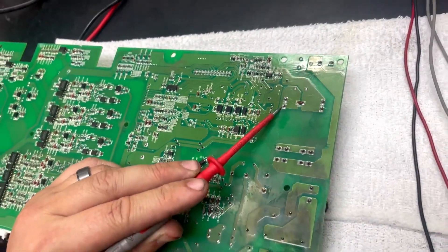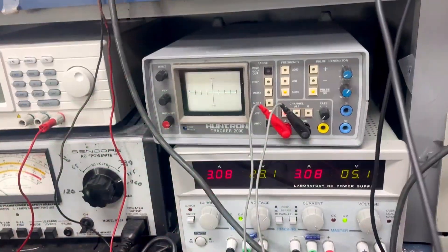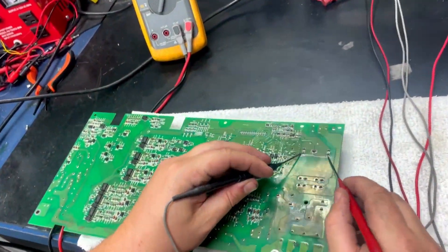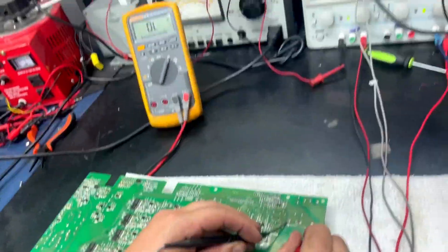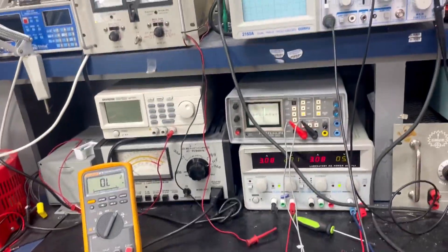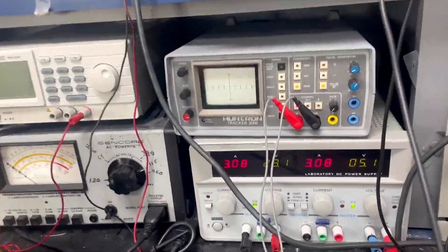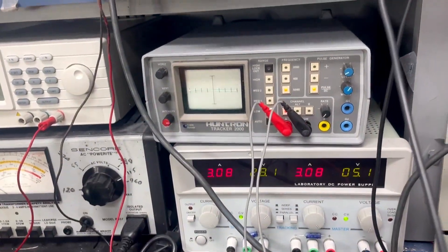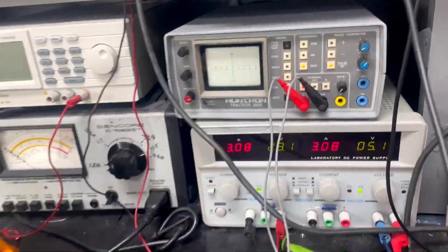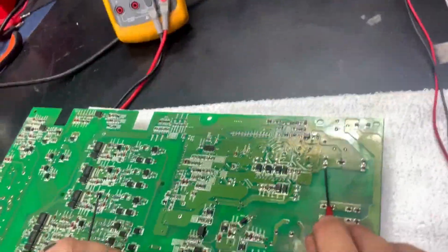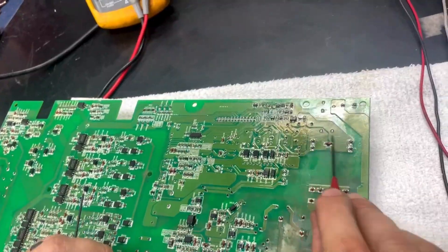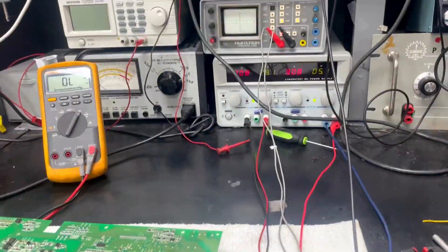So here is a test that we perform using our Huntron tracker. We can put our Huntron leads and examine the waveform. By looking on a Huntron, we can see the different waveforms as we measure across the coil. This tells us that this side of the circuit is where we need to put our positive voltage, and this side of the circuit is where we need our negative voltage.